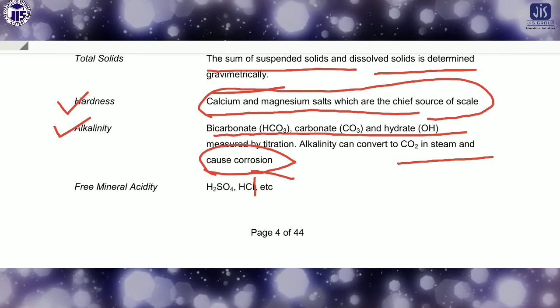Free mineral acidity: this is from H2SO4, HCl, which gives some kind of acidity. Then there are dissolved gases. Oxygen and carbon dioxide can be readily dissolved by water. These gases are aggressive and also very dangerous. So we have to think about the effects of the dissolved gases. As I already told you, dissolved oxygen is not very good for the boiler water, because oxygen is responsible for corrosion.